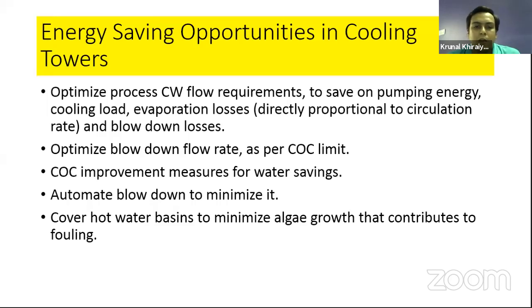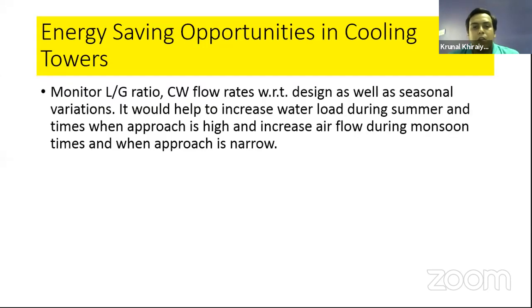Cover the hot water basin to minimize algae formation. Algae, all of you know, is very common. Sometimes fouling also contributes to loss of heat transfer. Yes, important is to monitor the L/G ratio, the cooling water flow rate with respect to design as well as seasonal variations.